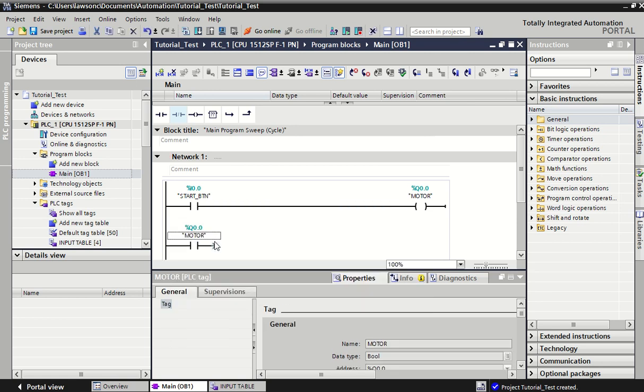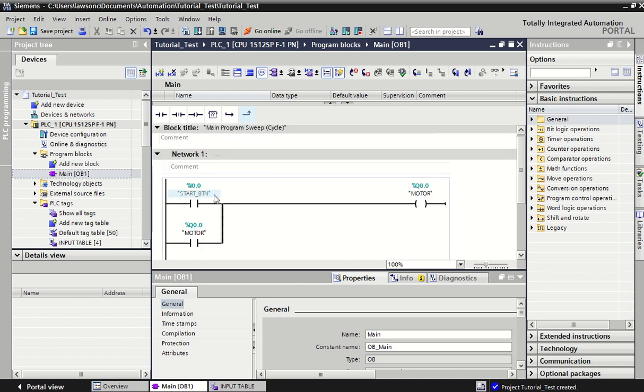What we can use is a monitoring bit of that output. I call my motor again, and this input will monitor whether the output is turned on or off — if it's on, this switch closes; if it's off, it opens. So if I branch that back in: when I turn on the start button, power can flow through to the motor. The motor hasn't turned on yet so it can't get power from the monitoring bit pathway. Once the motor turns on, its monitoring bit turns on and this input closes, looping power back around. Even if I turn off the start button, we can still get power through this pathway — and that's what we call a latch.